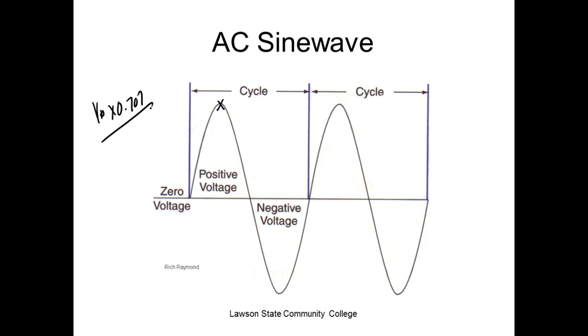But this only works on sine waves. If you get into non-sinusoidal waves, like ones generated by a variable speed or variable frequency AC drive, a regular meter won't measure the effective voltage. So we have meters called true RMS meters. These cost quite a bit because they have a microprocessor, they're computers, and they literally calculate RMS. These will measure the effective voltage no matter what the waveform looks like. If you're using a regular meter, you might get inaccurate voltage readings because it's using 0.707.